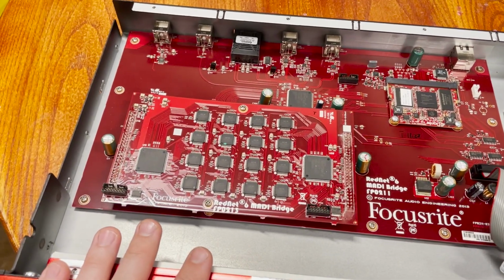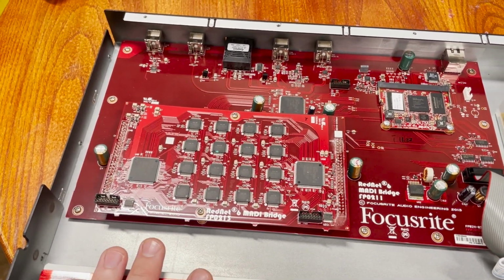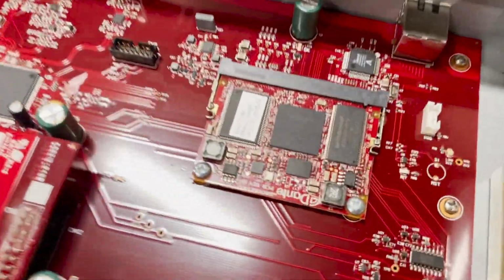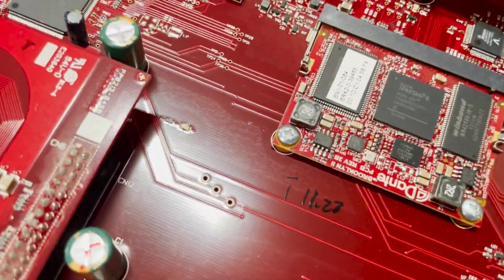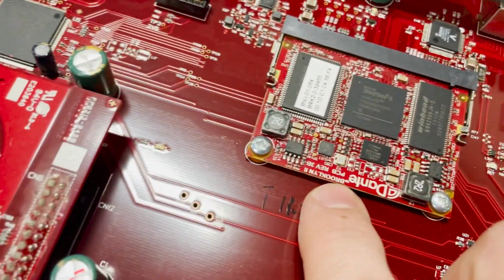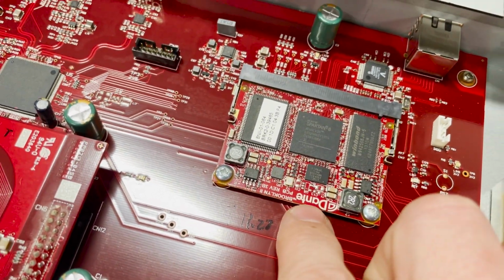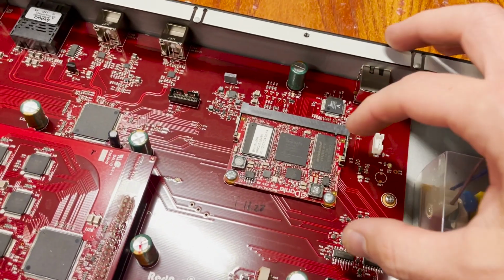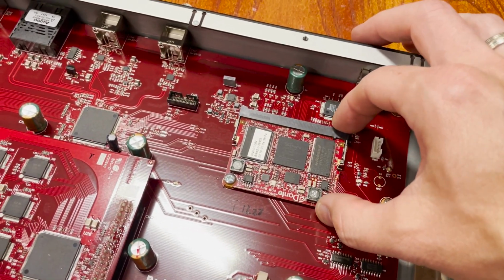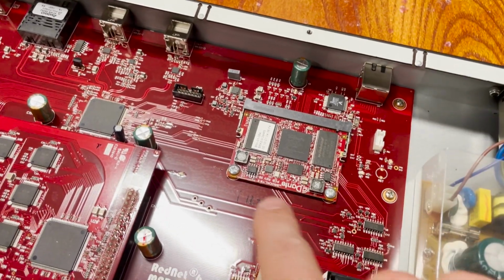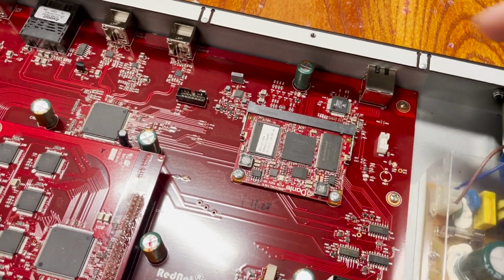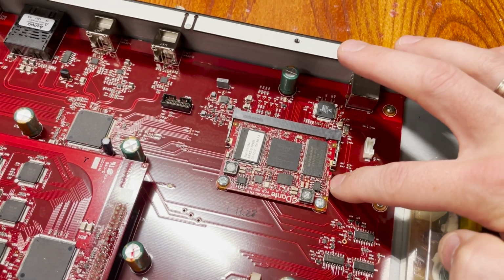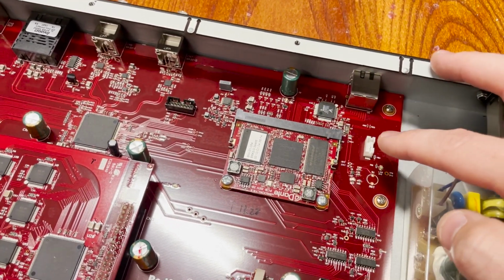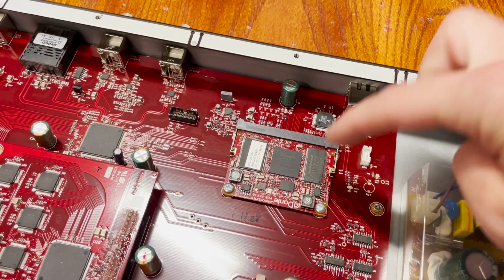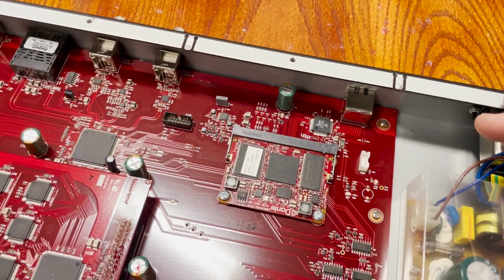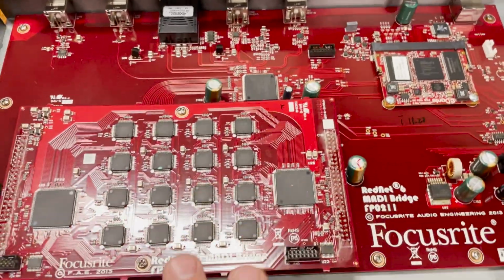This one is actually pretty clear about which is the Madi part and which is the Dante part. So this is the Dante card. This is labeled the Brooklyn 2 from Dante. And so this is the Dante card of this specific thing. And any Dante device is going to have a Dante card within it that's just interfacing the main motherboard with the Dante card. But every Dante device that you'll end up purchasing has a Dante card like this in a slot similar to this. So if you ever have a Dante card go bad, you can swap these. Little note.